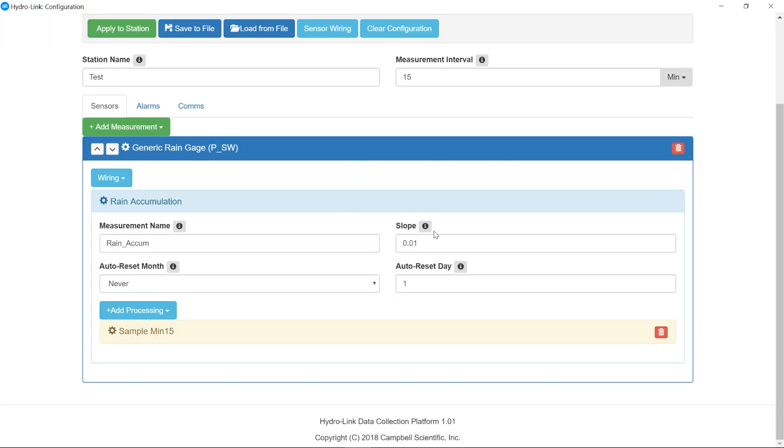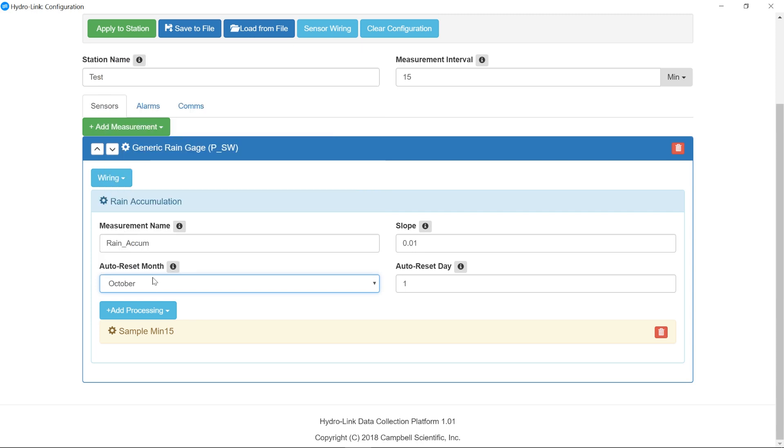Here I have a slope of 0.01 for 0.01 inches per tip. The name of the measurement is going to be rain accumulation. This option here is used to decide if I want to reset the accumulator automatically or to just let it run. And I'm going to set it to reset on October 1st, which is a hydrologic water year.